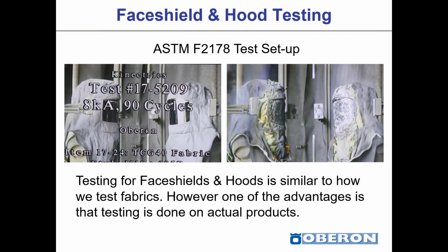The face shield and hood testing is a different setup. It's the ASTM F2178 test setup, again at the same high current test laboratory. The screenshot on the webinar currently shows on the left-hand side the test before it's conducted, and on the right-hand side, the arc flash hoods after they have been exposed to an arc flash. Testing for face shields and hoods is similar. However, the advantage of testing with F2178 is that we're actually testing actual products, which is fantastic for workers to know how the product they're going to wear for protection will perform based on the severity of the injury. This is different from a fabric test, where the fabrics are tested and the arc ratings are determined, yet we don't fully understand how the manufacturer may cut and sew the material and create the finished product that you're going to wear for protection.